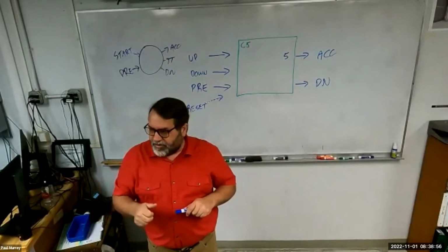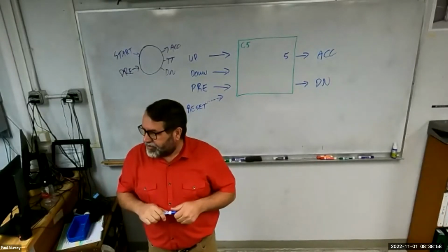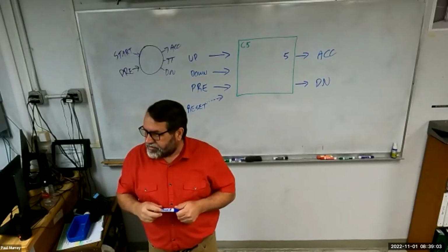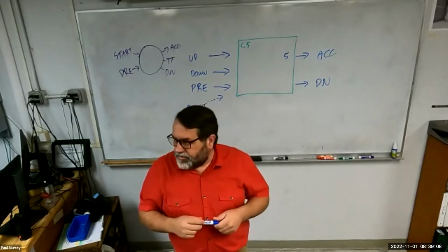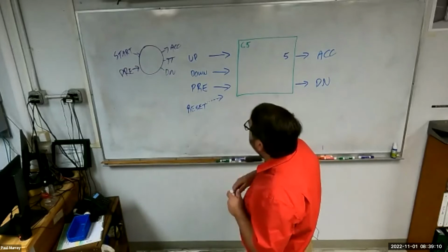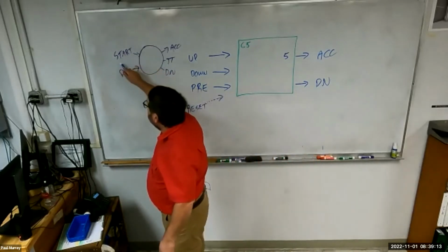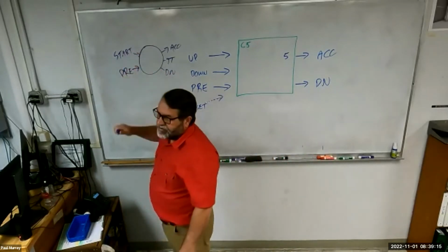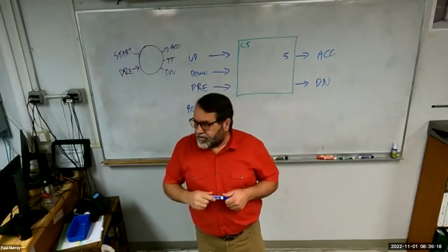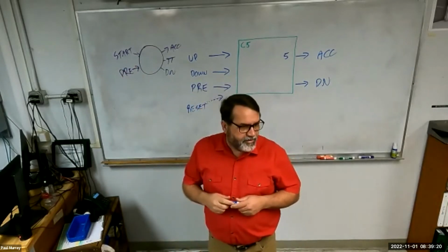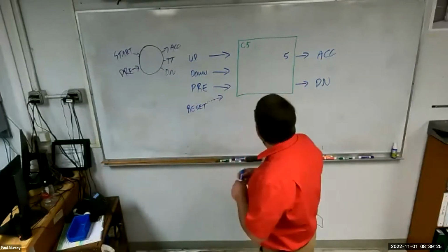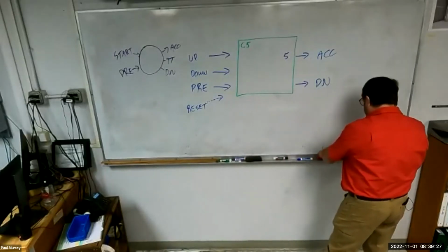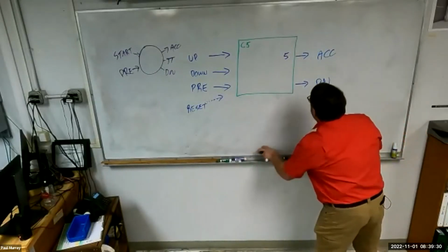And we're gonna get into, you said that timers reset on their own, so you can turn that off, right? By doing what? So when you use a timer, you have to somehow seal in whatever's making it run. So seal-in logic is the most common. But with a counter, you don't seal it in. Let me draw a little bit of these guys.